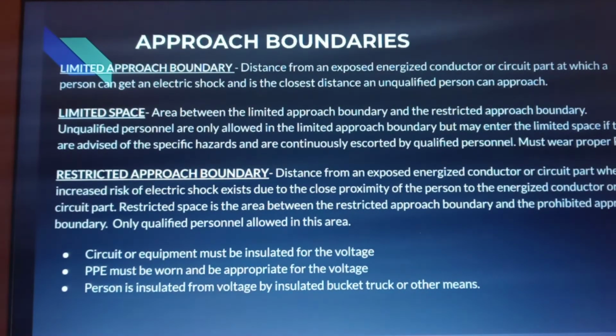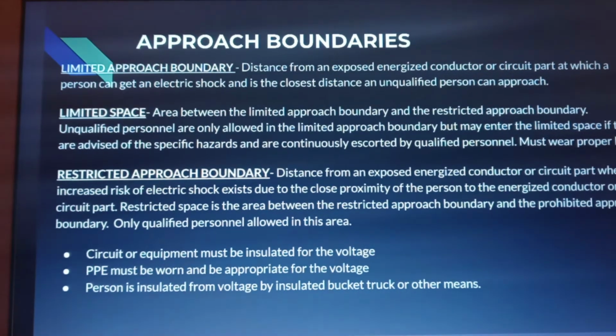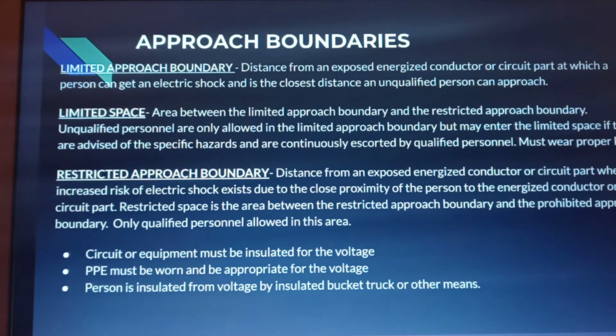All right, so what are approach boundaries? And what are all the different approach boundaries on this slide? It said a limited approach boundary is the distance from an exposed energized conductor or circuit part at which a person can get an electrical shock, and is the closest distance an unqualified person can approach. So just to reiterate that definition so that we can break it down a little more. The limited space is the area between the limited approach boundary and the restricted approach boundary where unqualified personnel are allowed in, but they must be advised of the specific hazards and are continuously escorted by qualified personnel. You also must wear the proper PPE to be in the limited space.